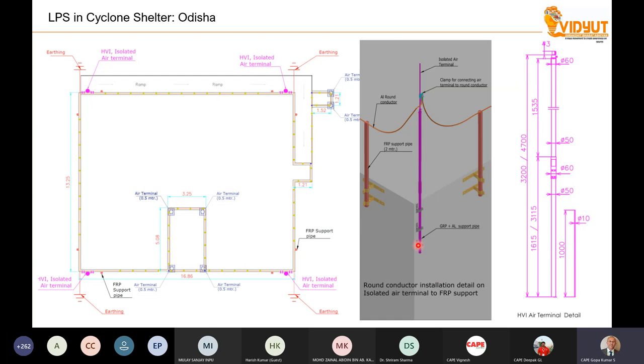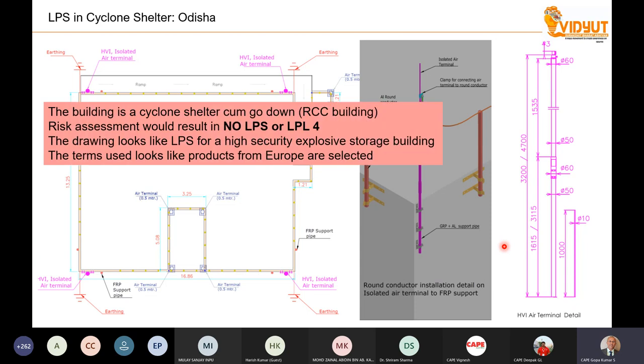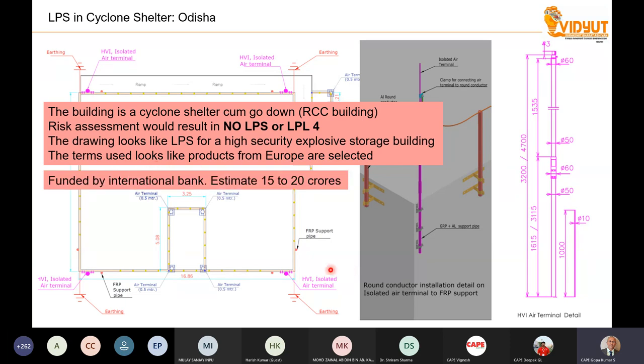The question is, what are we doing? Who proposed this? Even without air termination, probably the people are protected. And this kind of an isolated protection is required, let us say, for example, in a defense installation where missiles are kept inside the building. Very special cases, you need to have this kind of a very expensive isolated lightning protection system. But somebody, I'm sure some European manufacturer, very cleverly put in these unwanted things. As a result, there was a big tender. It is a cyclone shelter. If we make a risk assessment, probably no lightning protection is required for this building. Even if it is required, probably lightning protection level 4. The drawing looks like an LPS for a high security explosive storage building. The terms used look like products from Europe are selected.